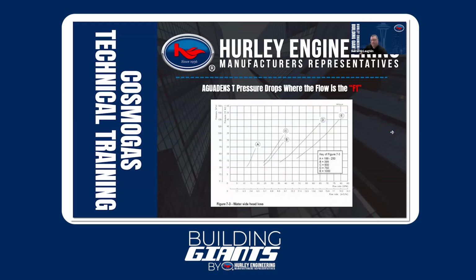Now, once I've done that, I can go over here to my pressure drop chart, again provided in the manuals, and I can take that across and I can follow my flow up and find what the head loss is of the heat exchanger at that flow rate. So again, that would be my minimum. I could take that head loss and then I could take that to my pump curves and I could size it accordingly and find out what pump I need in order to accomplish that task.